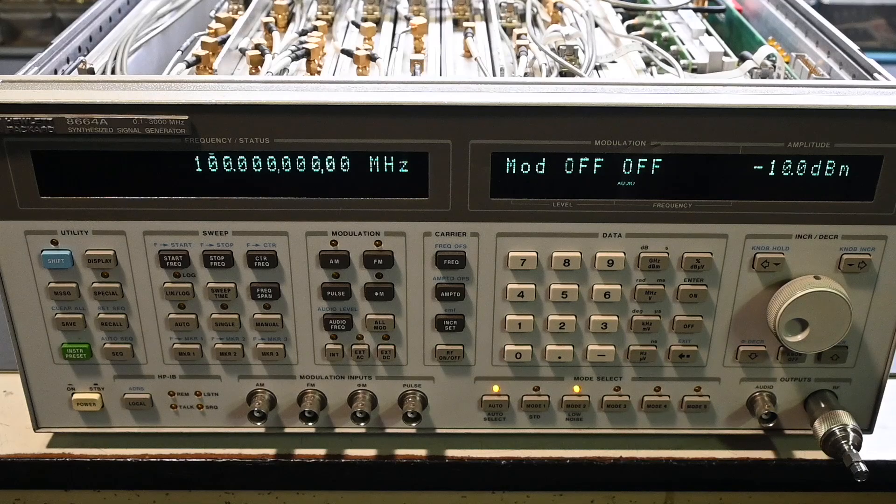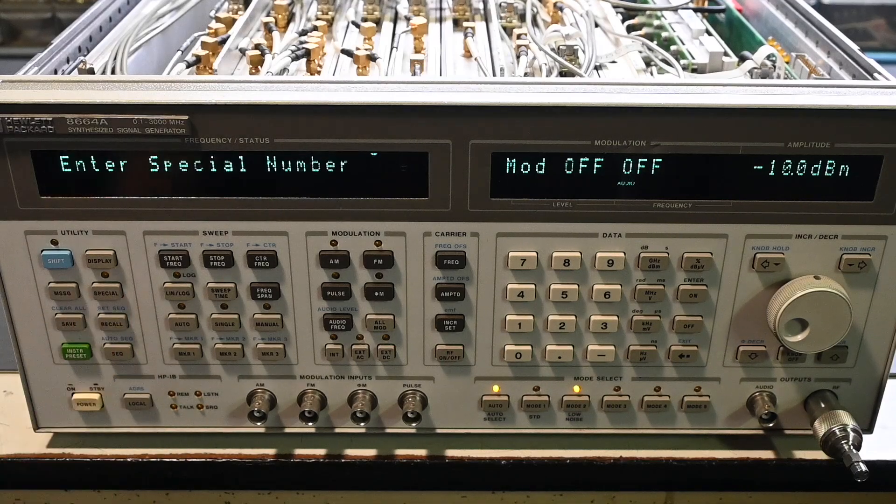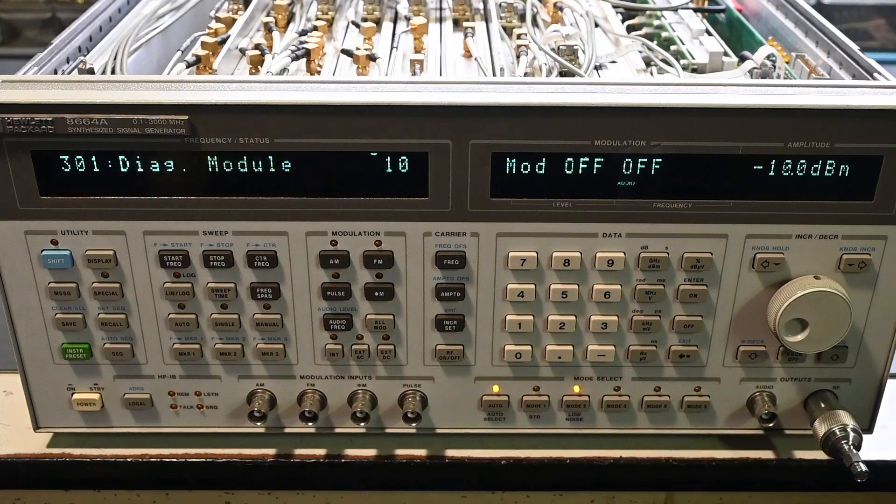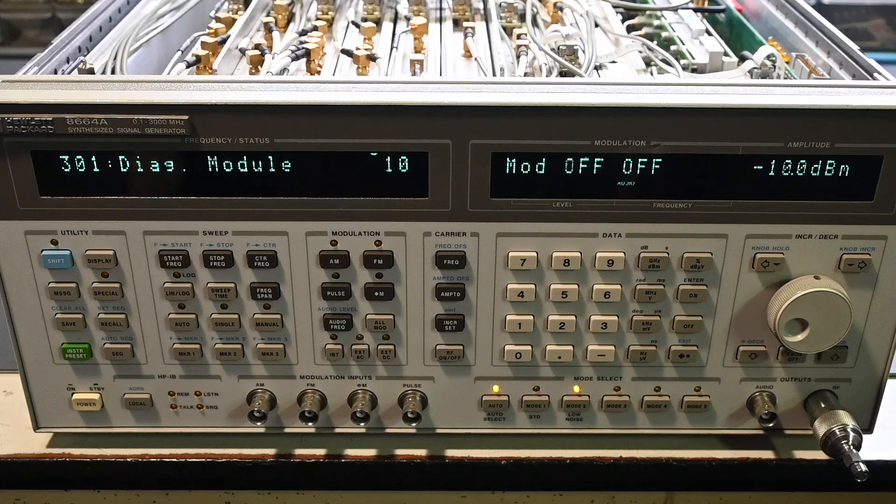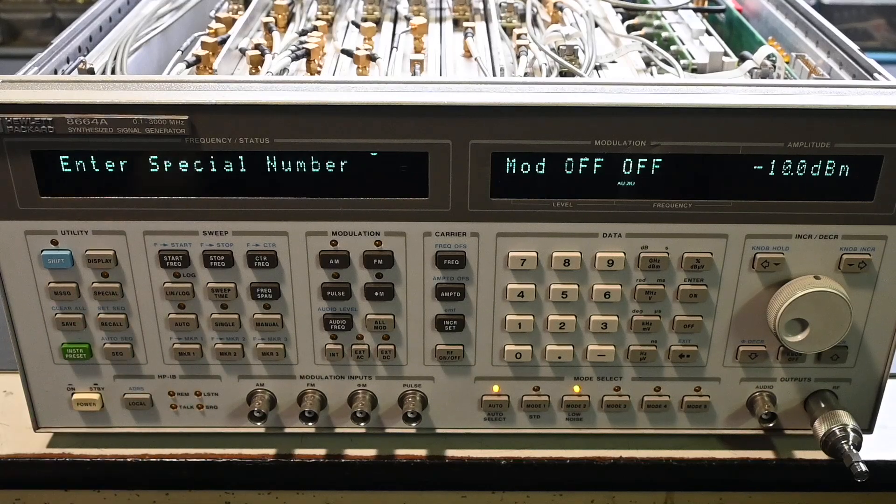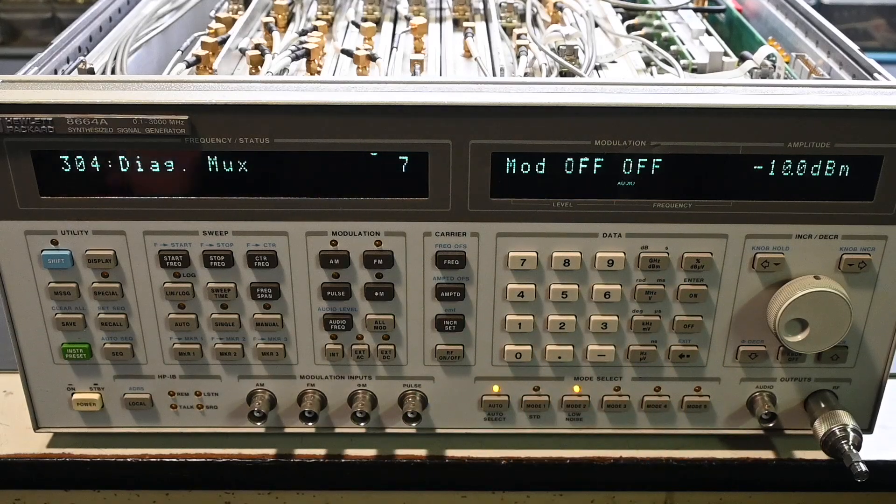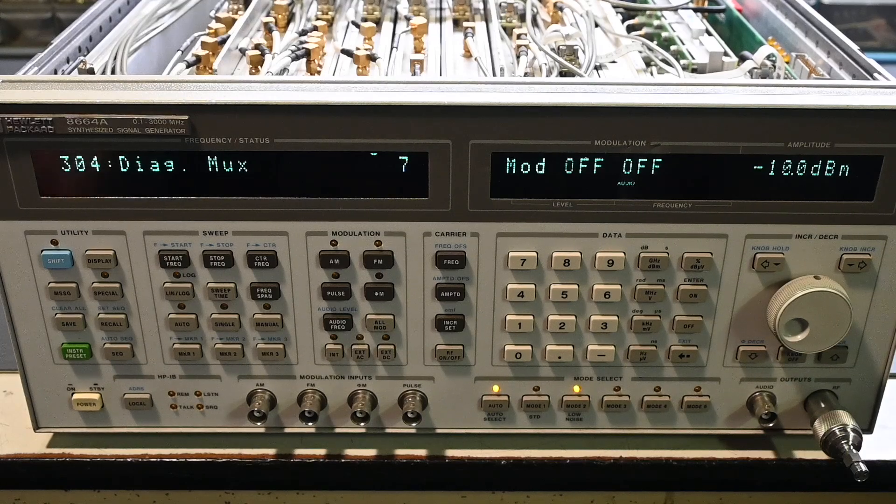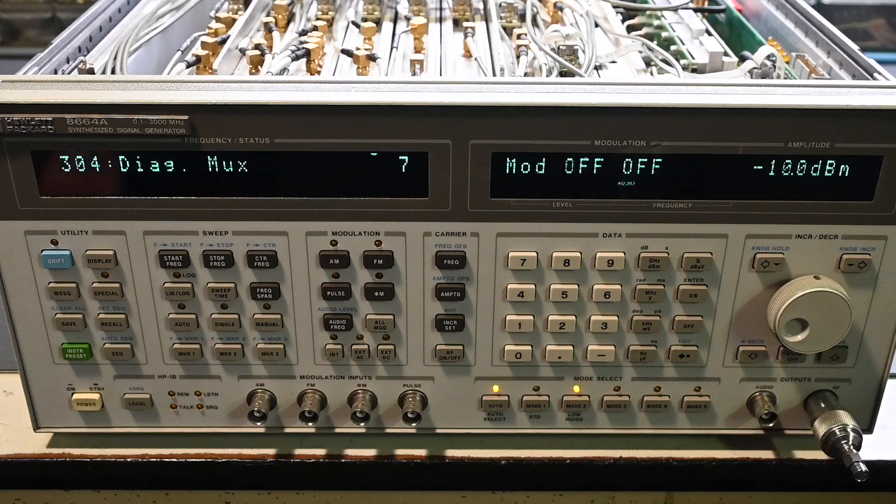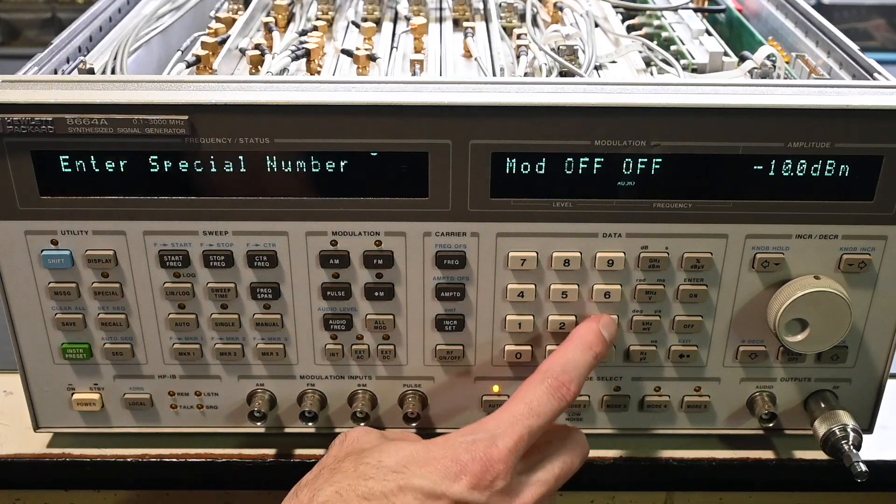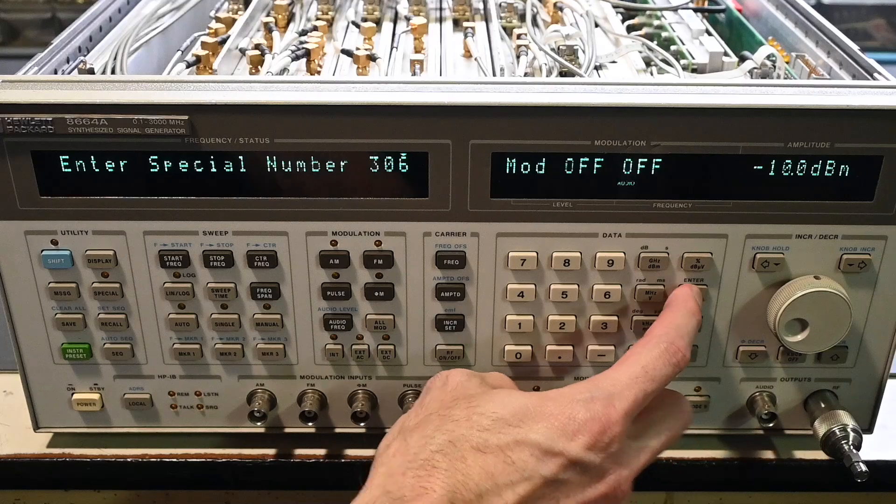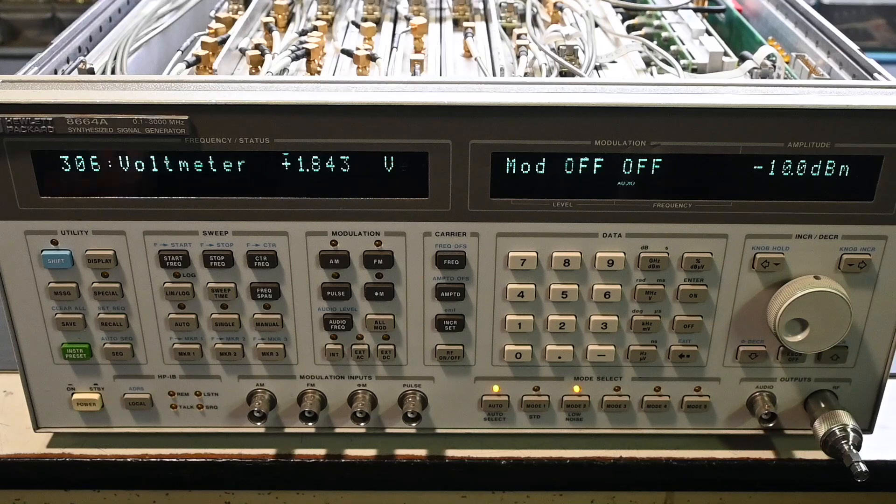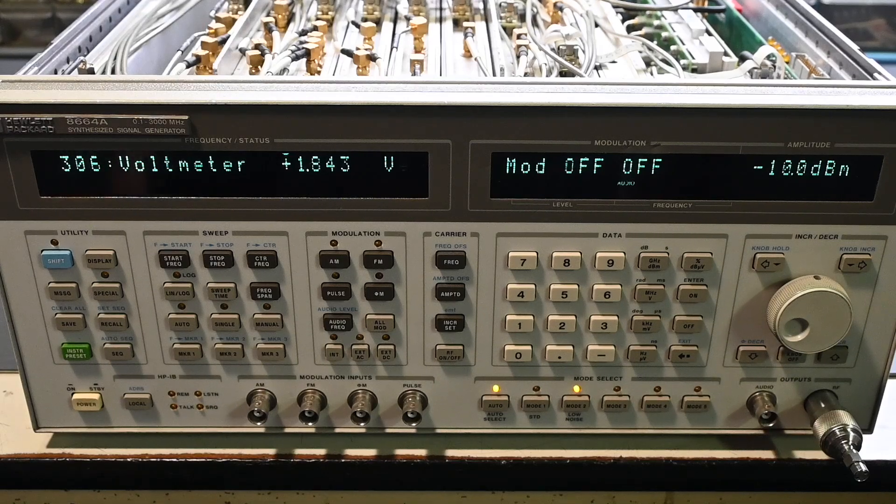So taking a look at this setting right here, if we go to the special menu, and then if you do special 301, that's the module and it shows module 10, that's the HF driver module that it's going to take the measurement. And then if we go to special 304, mux 7 or multiplex number 7 is the test point that we need to take the calibration reading at. I know it's mux 7 because of the service manual and the information that was given there. And if we go to special 306 and turn that on, there's the built-in voltmeter, and it's already in the DC voltage mode.